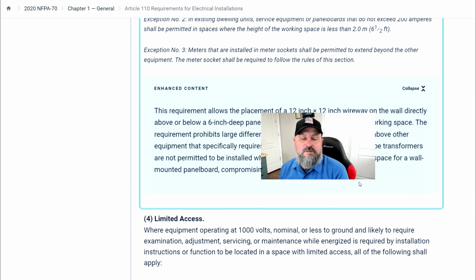So there is a stipulation in here that you can't put a much deeper gutter or box in that 6.5 feet space near a panelboard, because that encroaches on the workspace, and you can't hang a dry transformer above it either.